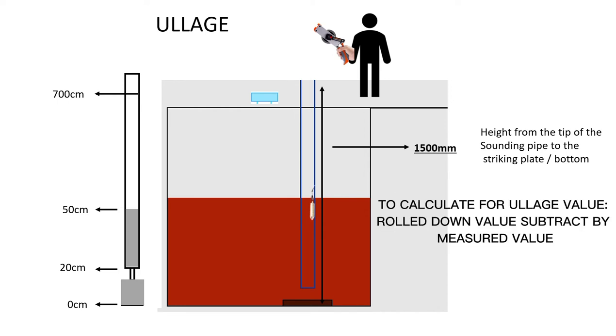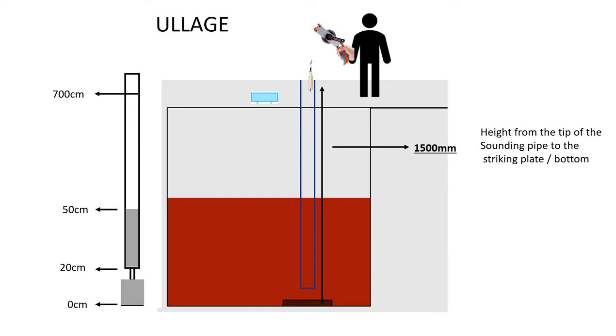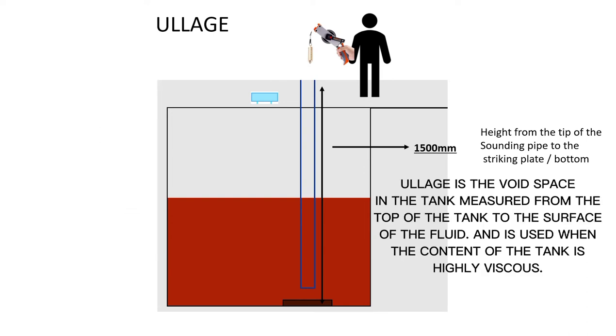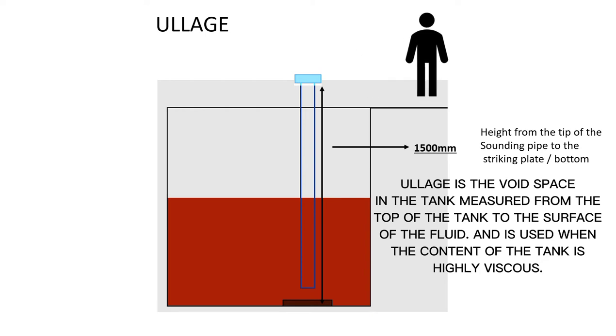To calculate for ullage value: roll down value subtract by measured value. 700 minus 50 equals 650. 650 cm is the measured ullage. Ullage is the void space in the tank measured from the top of the tank to the surface of the fluid and is used when the content of the tank is highly viscous.